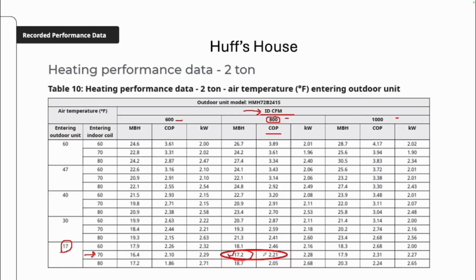So think about that. Hopefully you see that measuring airflow, then measuring delivered capacity using those airflow numbers, and then comparing that to what the manufacturer says the system is supposed to be doing can either A, satisfy the end user, or B, uncover a problem that will send you to find out what's happening with the system, or C, it may be that the delivered capacity matches the chart, but then you may have to go deeper. Maybe that system is not sized correctly for that home, or maybe you do have massive duct leakage somewhere, and you're not delivering that heat into the space. But for me, it always starts with verifying the equipment operation first and then working my way out. This process has served me well over many years. It's very simple, but it works.